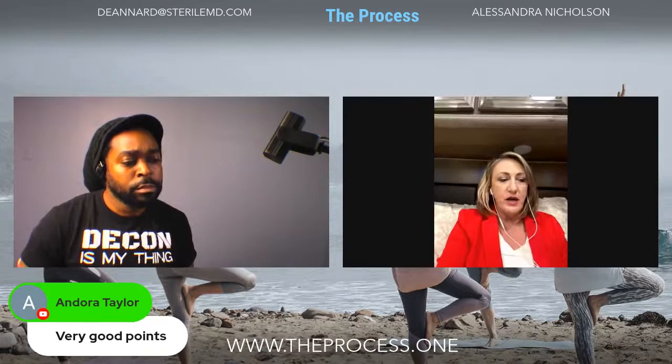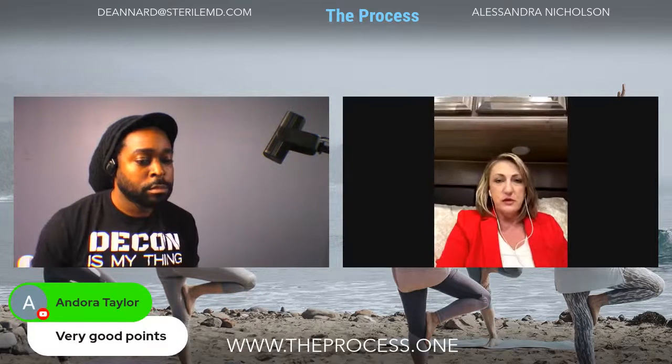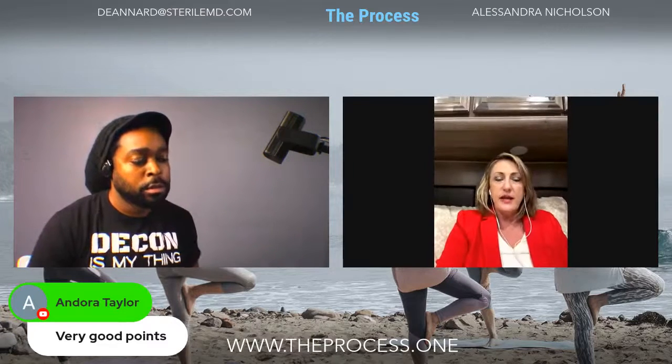The floor repair. We've had several people and we've gone in as consultants and told them you need to replace the floor. But, you know, floor's coming up. You can see the concrete and the concrete's deteriorating underneath because it's a wet area, and they don't do it. And then they get written up for it. So it's things like that to look for: flooring, rust.